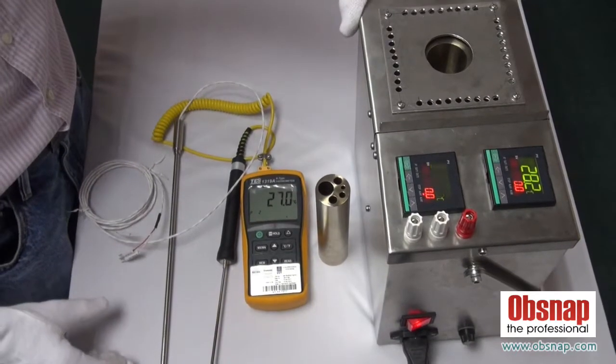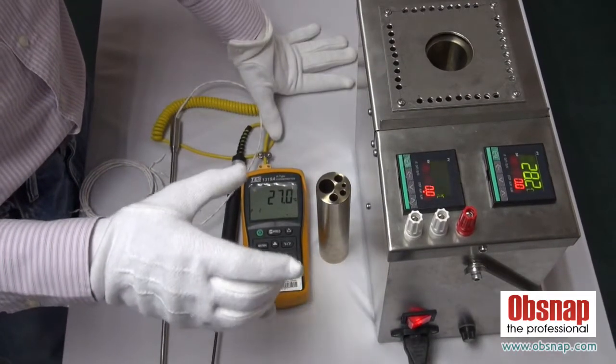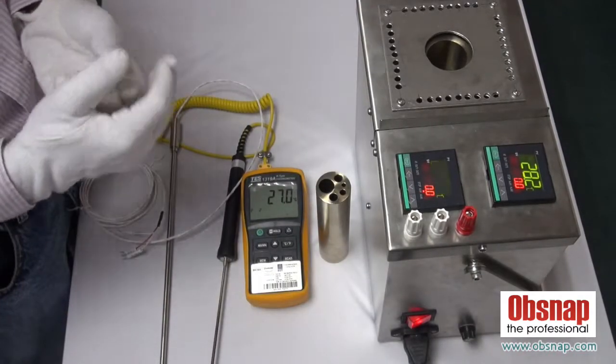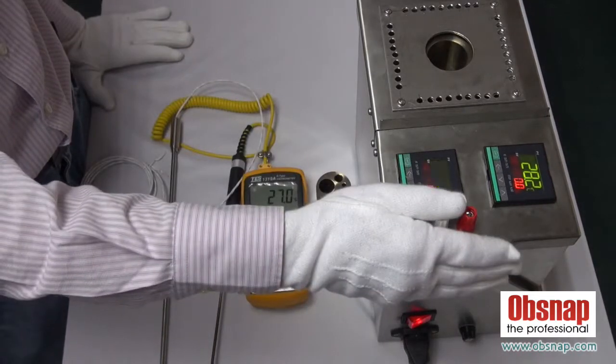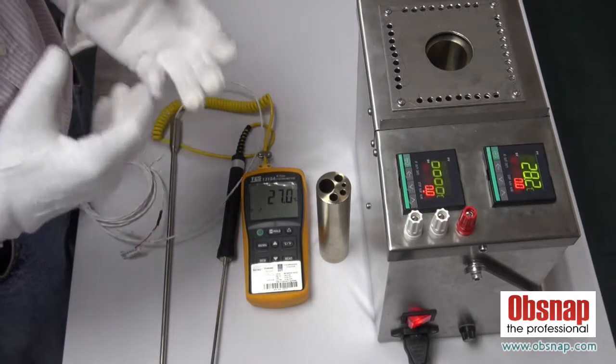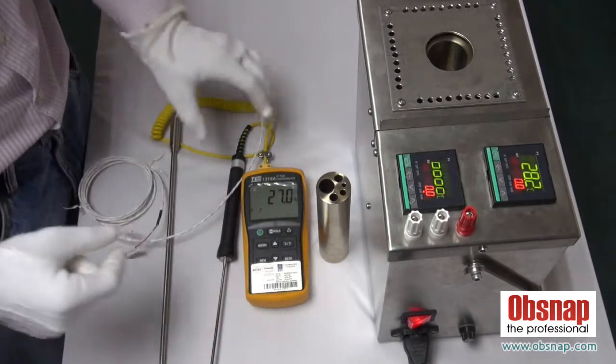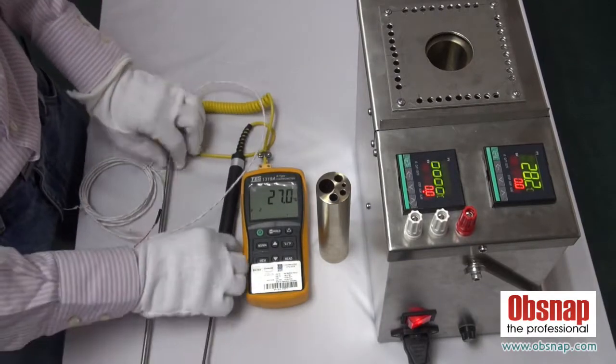Today I would like to show you the basic operation of the dry box, or some are calling this temperature block calibrator. The function of the dry box is mainly to produce heat to perform the calibration of the sensor.